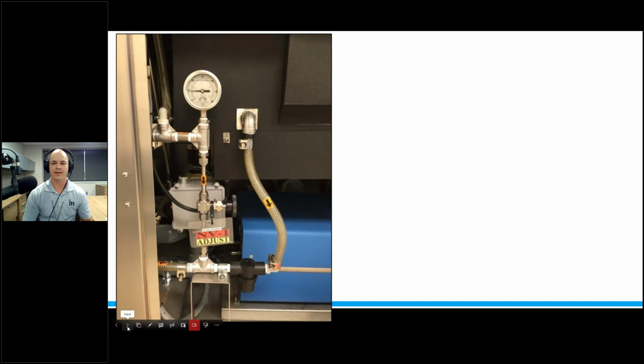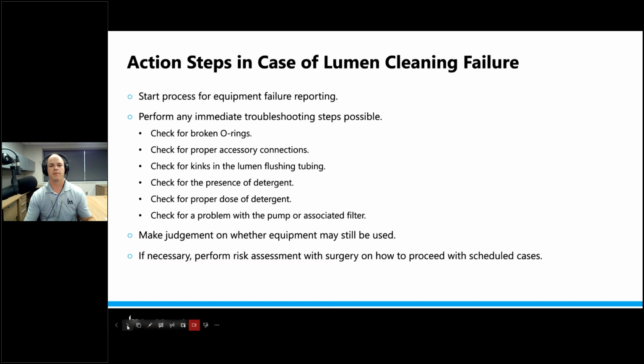Whereas, in my case, one time it happened at the hospital I worked at, the lumen cleaning function failed, but the cavitation and soil removal test passed. And I had a second ultrasonic cleaner. So I was able to divert all the lumen instruments that needed to be hooked up to the lumen cleaning function into the other sonic where it was actually working. And then we could still use the one where the lumen cleaning function was broke or not functional at the time. We still used it for regular standard instruments that were not lumen.